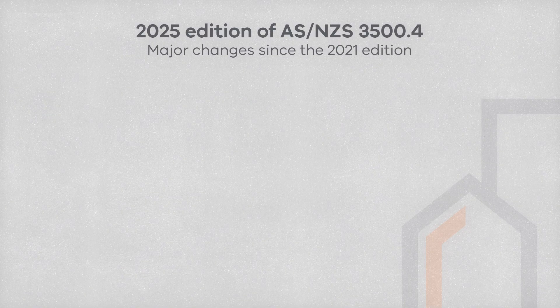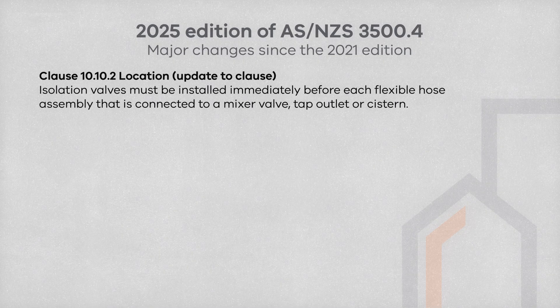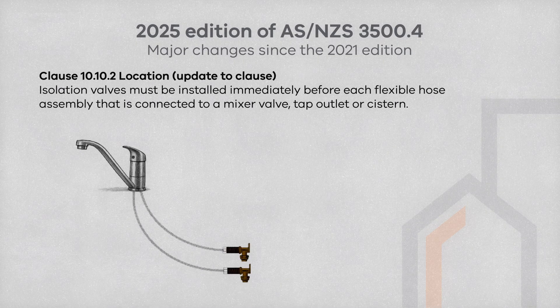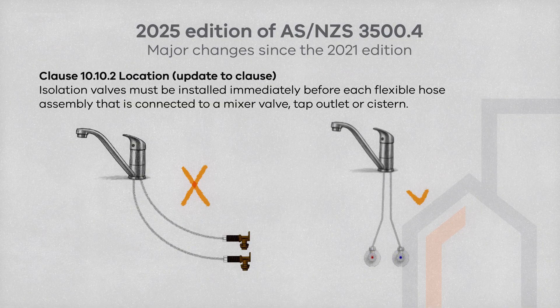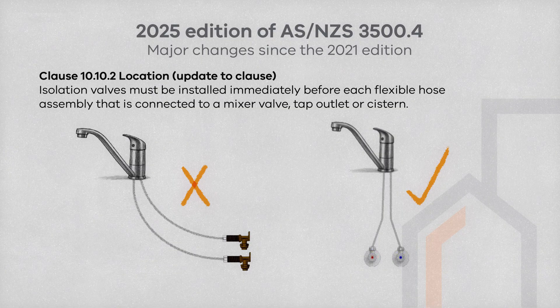Similar to Part 1, Clause 10.10.2 in Part 4 includes the addition to the location of isolating valves. It states that an isolation valve must be installed immediately before the flexible hose assembly connected to a mixer valve or tap outlet. This applies to circulatory pipe plumbing systems.